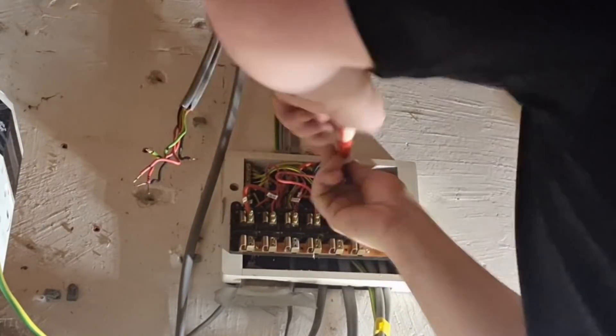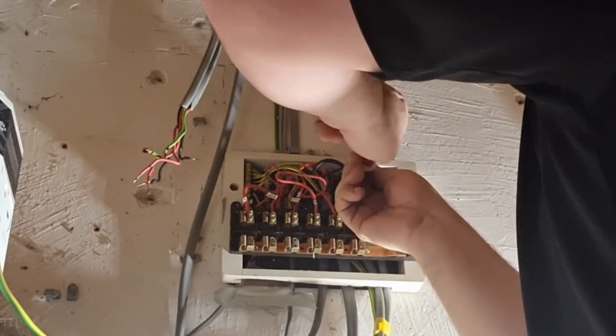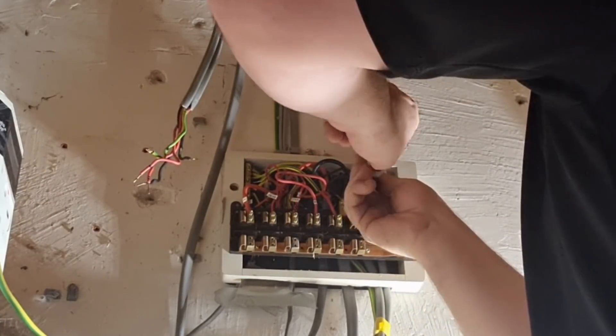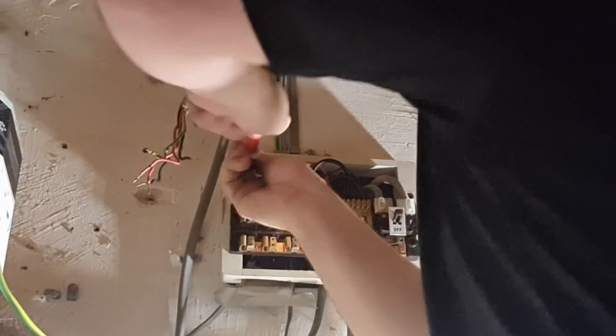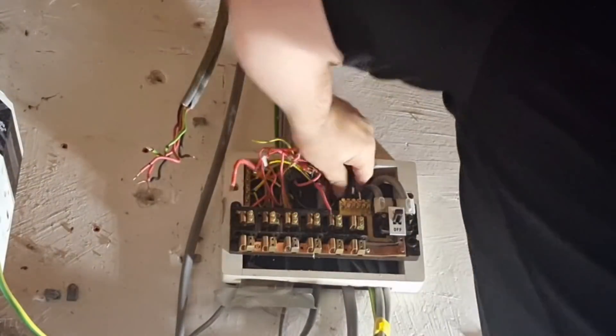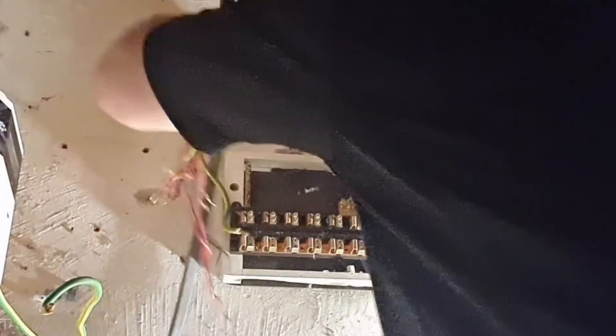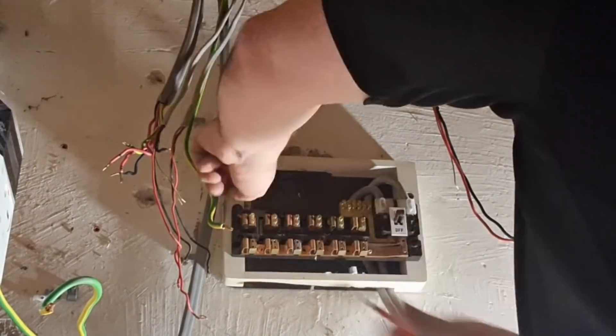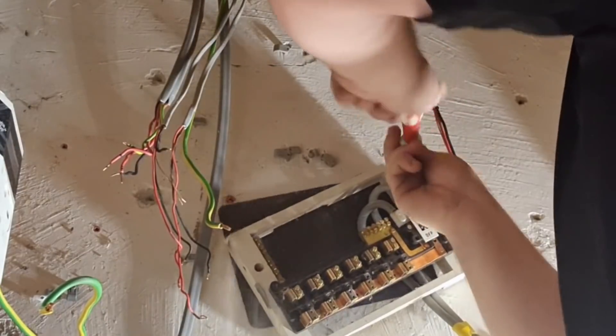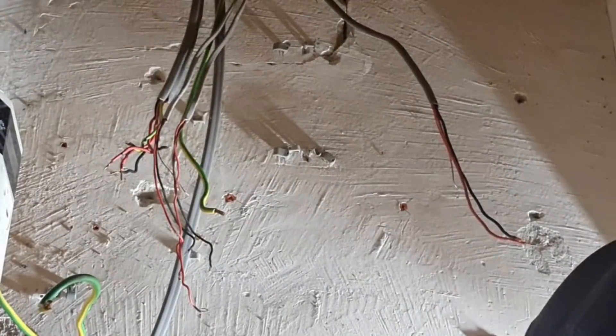It just needs a bit better overcurrent protection at the main intake, so that's what we're doing here. We've also got our hot tub circuit to install because there was no spare ways on anything. We would have had to put a third board in, so the customer's just decided to bite the bullet and get the whole lot upgraded to a modern RCBO consumer unit with an SPD.